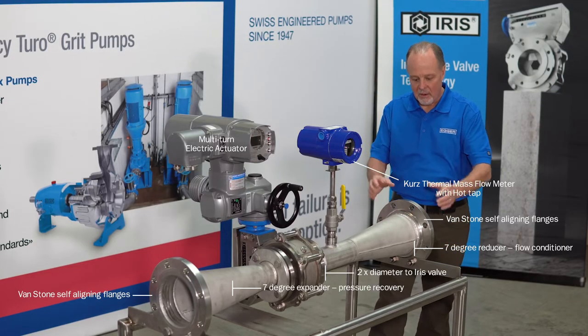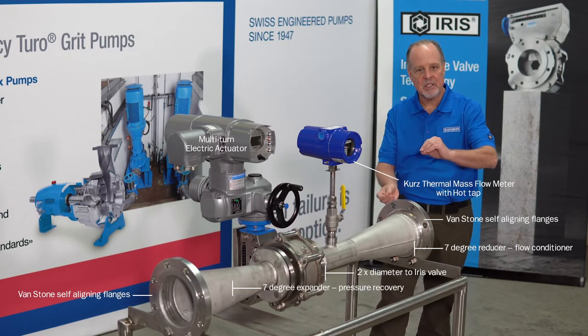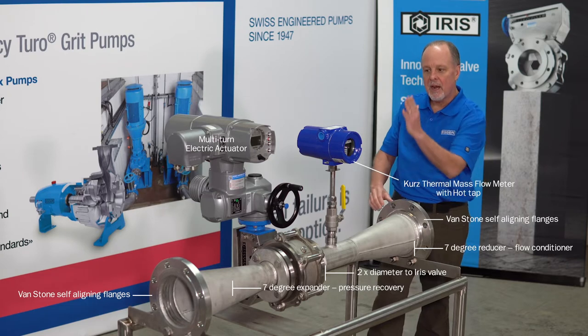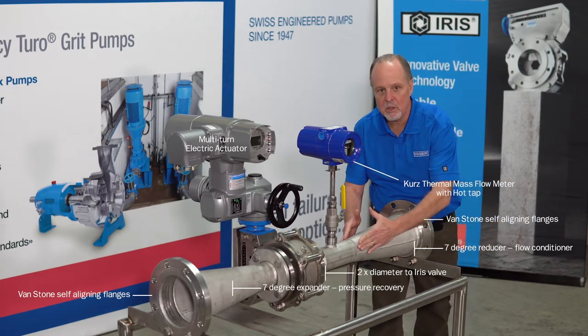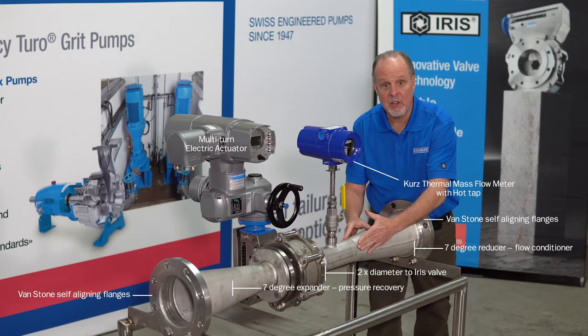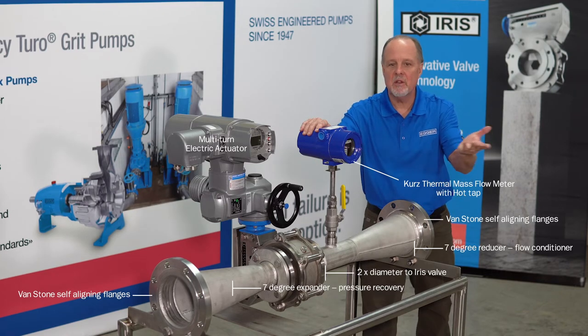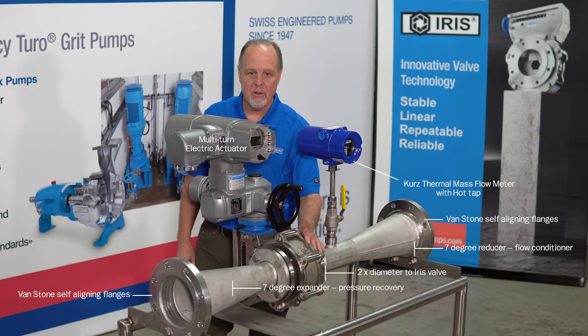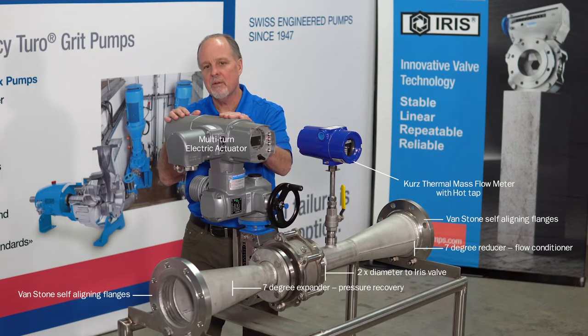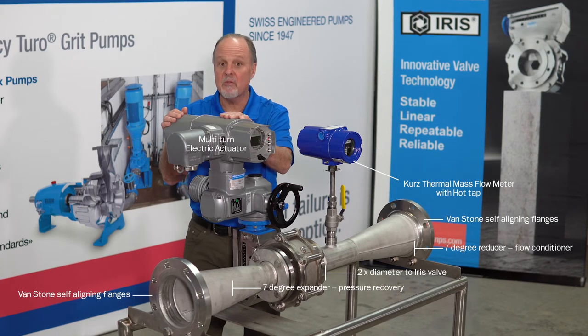Moving along, I've shown you the Vanstone flange, which is a flange that rotates to allow you to align everything vertically. We've talked about the 7-degree reducer, which actually is a total of 14 degrees — 7 degrees on each side. Then a quality flow meter similar to the Kurz, two diameters to the valve, and then a quality actuator. I don't care if it's Auma or Rotork — they're both very good.